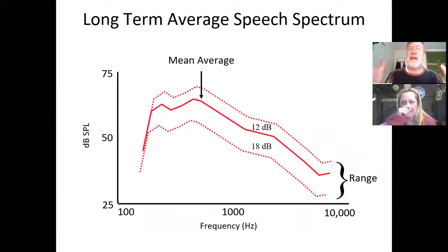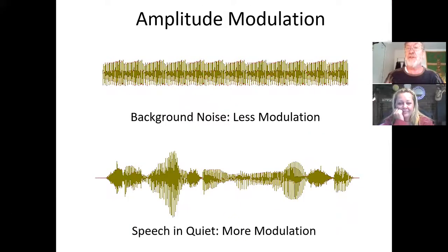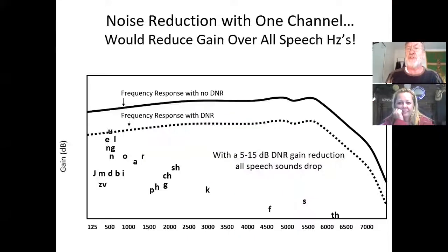We said digital hearing aids use all this kind of stuff to tell whether it's noise or speech. They're using math. We don't. I'm a normal guy, I can't think like this, but digital algorithms do. They're using math to determine, hey, is it live or is it Memorex? Is it this or is it this? They look at all these things together to determine whether to reduce the gain in any one particular channel. We said that's why you don't have digital hearing aids with one channel, because otherwise you're just reducing the gain for everything.